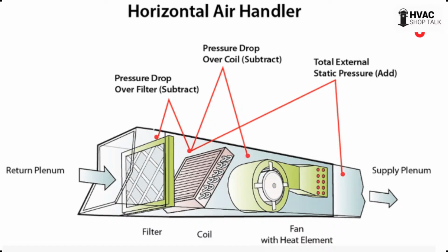Now, the reason it's between the filter and the coil is because that filter is added at the job. And when a machine states what its total external static pressure is, and you go to the charts, it does not include stuff that does not come with it. So if you're adding filters to the back of the air handler, for instance, like the media filter we were just talking about, you have to measure that return side static pressure in between the filter and the coil.